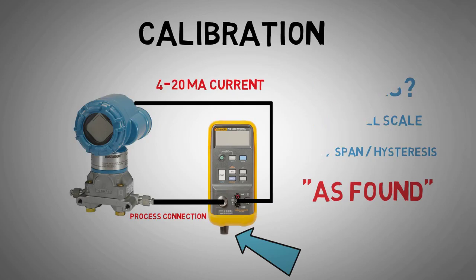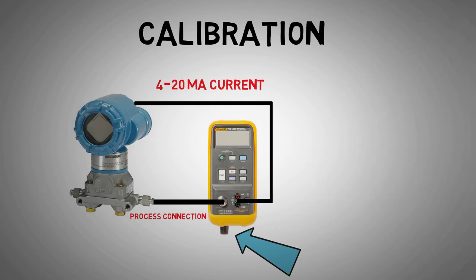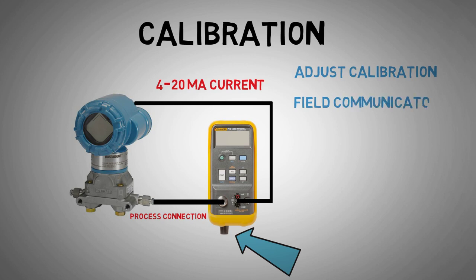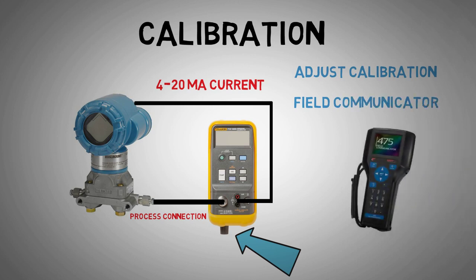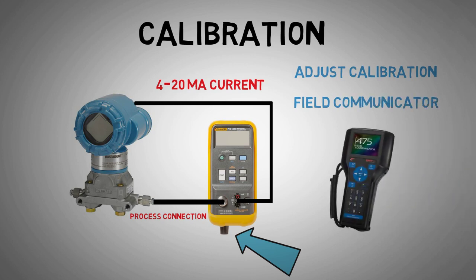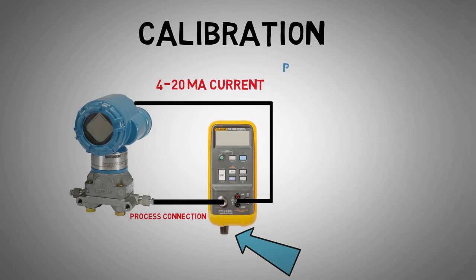If the pressure transmitter is out of its calibration limits, we would adjust the range or zero either through local potentiometers or buttons on the transmitter, or more commonly on newer equipment, digitally via a field device communicator such as a HART. We would then repeat the test to ensure we have met our calibration standard. This is called the as left test.